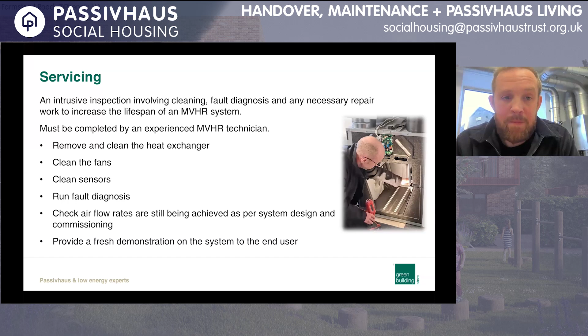Servicing is also a great opportunity for us to provide a fresh handover to the client. So often, when we commission the system, we give a handover to the client, but they've also got a lot of other things to consider. There's the air source heat pump commissioning, there's the actual physical moving in of the house. So it doesn't always sink in. So 4 years later is a nice time for us to say, right, here's how to use it again. Any questions that they've got, we can answer. And we also suggest it for new tenants, and also if anyone buys a house with an MVHR system, we suggest servicing to make sure it's clean, but also to tell them what it's doing and how to use it.